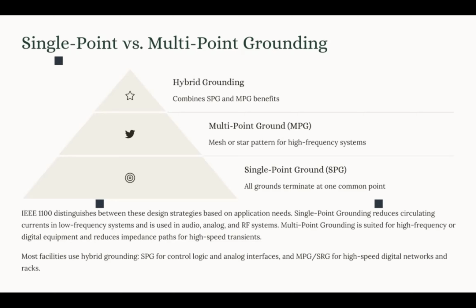We said there's a third topology, which is hybrid, a combination of the single point and multi-point. It is meant to balance the advantages and disadvantages of both. In most modern facilities like data centers, aerospace or hospitals, we normally use that hybrid grounding because systems normally have both analog control circuits and high-speed digital electronics. So we need both aspects, the advantages of the multi-point and single point grounding.